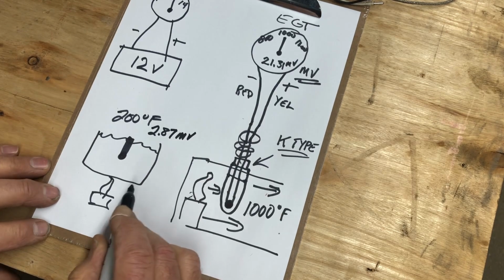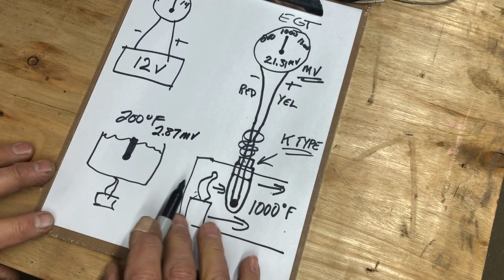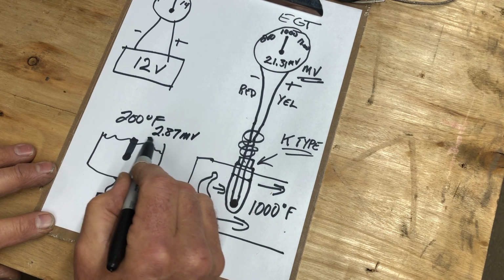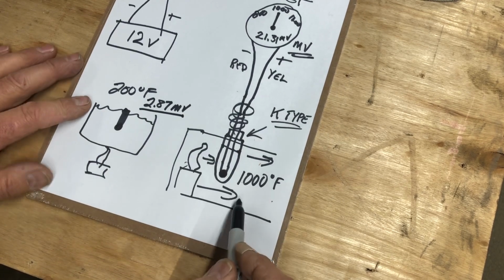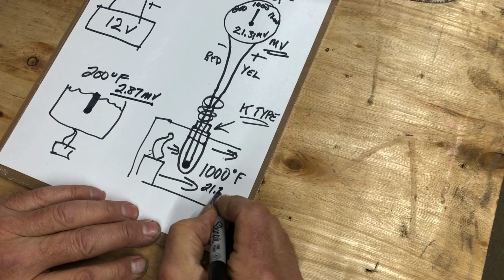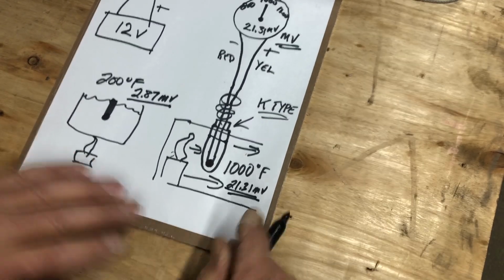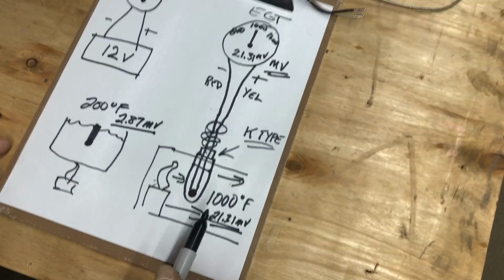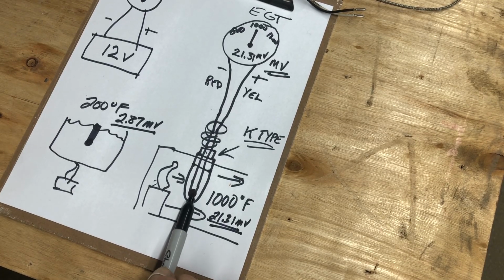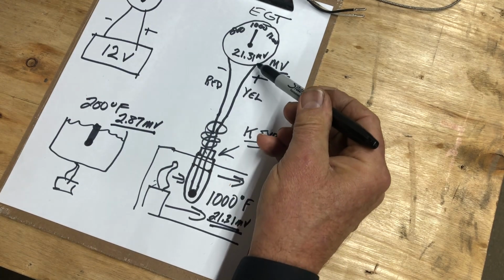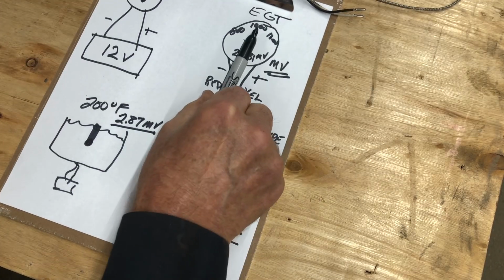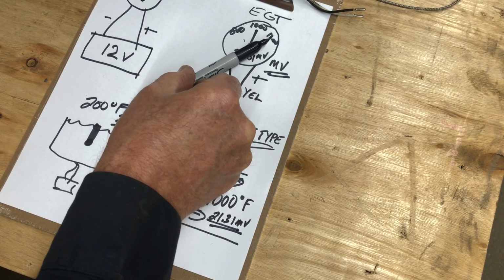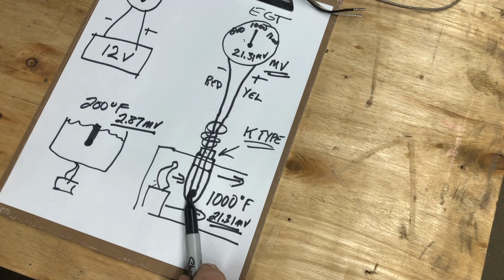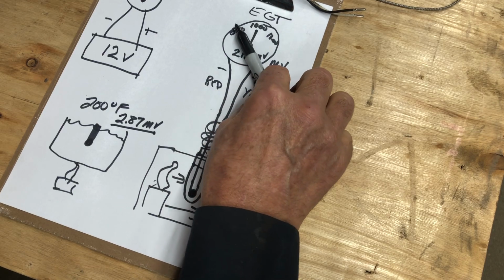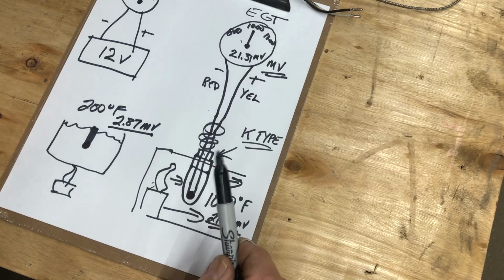2.87 millivolts. So here's the span on this, it works with such low voltages: 200 degrees is 2.87 millivolts, 1000 degrees is 21.31 millivolts. Very interesting how it works. The hotter this point, this little bead of weld, gets, the more voltage it produces in millivolts, and it deflects further toward, say, 1200 degrees. Take away some heat, close the throttle, less work is being done, the exhaust cools off, and it'll deflect down and read 800 degrees, at whatever the corresponding voltage is.